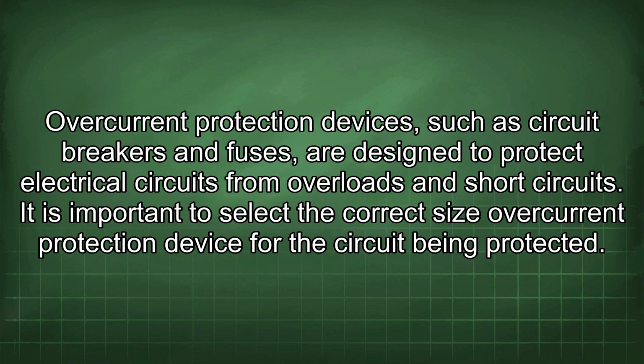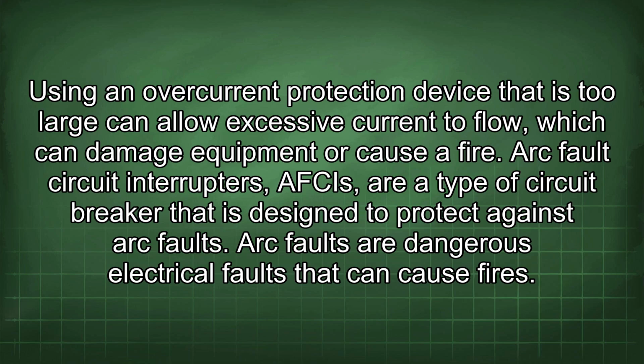Overcurrent protection devices, such as circuit breakers and fuses, are designed to protect electrical circuits from overloads and short circuits. It is important to select the correct size overcurrent protection device for the circuit being protected. Using an overcurrent protection device that is too large can allow excessive current to flow, which can damage equipment or cause a fire.